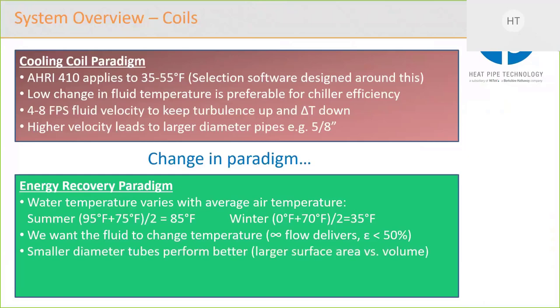The other thing, as we've seen in the refrigeration industry, is that smaller tubes perform better, because as you go to a smaller diameter, the ratio between the surface area and the volume of that pipe gets bigger. You have more surface area for heat transfer for a certain amount of liquid in there. So as a result, we've looked at trying to keep the velocity through the coil down below 3 feet per second.